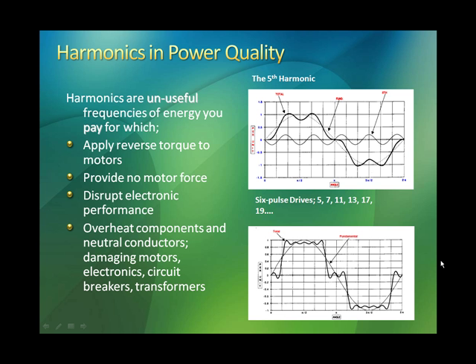When you combine the two waveforms, that small ripple in the middle and the nice clean dotted line AC waveform, what you see is the result there on the screen, something that looks like a camel's back, a distorted AC waveform. That is called total harmonic distortion, and how badly it's distorted will increase the percentage of total harmonic distortion, or THD. And that is, again, damaging. It's something that most industrial facilities today face because of the use of these high efficiency electronic drive packs that drive motors and use less electricity, but they do put these harmonics onto the line.